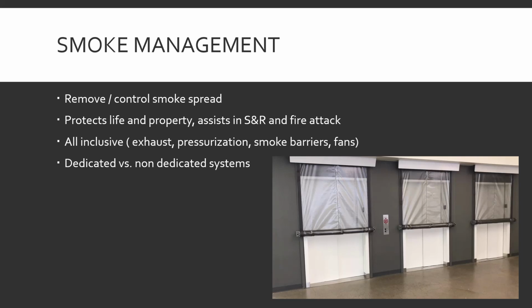And it's all inclusive. Exhaust fans, sucking air out of the building, blowing it out, smoke goes out, problem solved. Pressurization, pressurizing different parts of the building. The smoke can't go from an area of low pressure to high pressure. Kind of like clean rooms in hospitals. So by pressurizing stairwells, which is a common one, when you get in the stairwell there's no smoke in there, because all the smoke is in the building. But you're trying to keep the stairways clear so people have air to breathe while they get out.